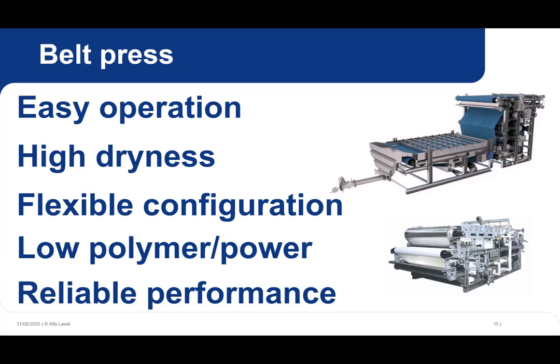The thickened product then moves into the pressure zone of the belt press and is squeezed between high-pressure rollers that gradually decrease in size. More advanced designs on the market will allow for adjustment of the wedge prior to the pressure section, as this will control the initial shear that the product sees. After pressure is applied, dry cake then exits the press and the belts are cleaned with a spray bar. The belt press is a very common method used by thousands of wastewater plants around the world. They continue to evolve, adding new performance features and capabilities. We'll talk more about some of these innovations in just a few minutes.